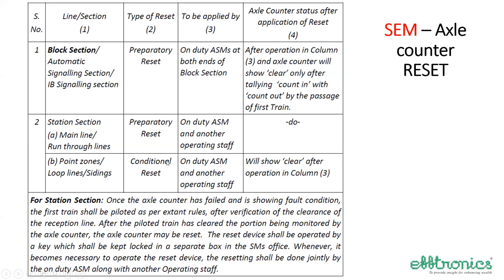What is conditional reset? This is hard reset, that means immediately it changes to the clear mode. On-duty ASM and another operating staff. This other operating staff goes to that particular place and there is a thing called line verification box. He presses that button. Because the condition is that the LV button has to be pressed. Line verification button has to be pressed by another person in the field, that is the condition. That is why it is called conditional reset. I think I am clear.